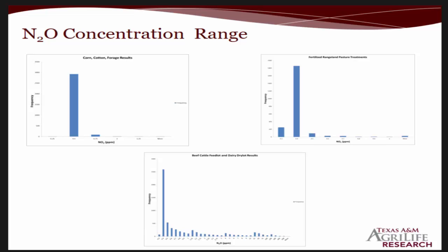If I was just doing this work, I'd have the GC set up differently, and my minimum detectable level would be lower. If I set things up to just handle 1.5 parts per million as my maximum, my minimum detectable quantity would be lower. If I tried running this on a GC I'd optimised for doing that, the detectors would be swamped.